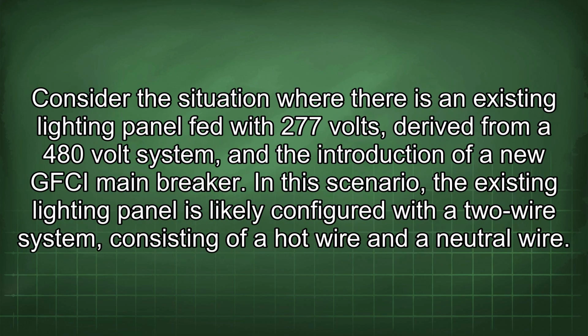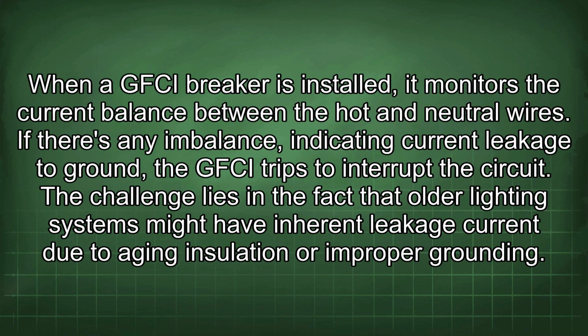Consider the situation where there is an existing lighting panel fed with 277 volts, derived from a 480 volt system, and the introduction of a new GFCI main breaker. In this scenario, the existing lighting panel is likely configured with a two-wire system consisting of a hot wire and a neutral wire. When a GFCI breaker is installed, it monitors the current balance between the hot and neutral wires. If there's any imbalance indicating current leakage to ground, the GFCI trips to interrupt the circuit.